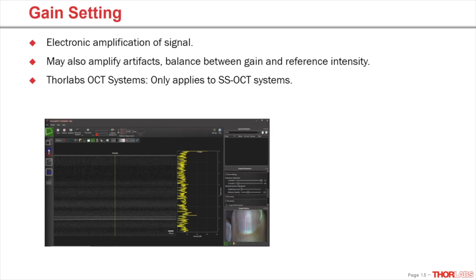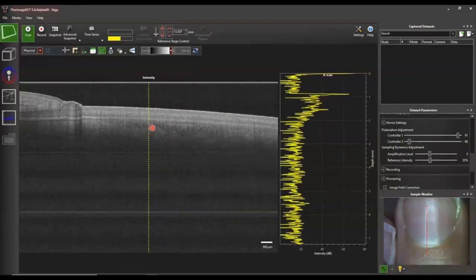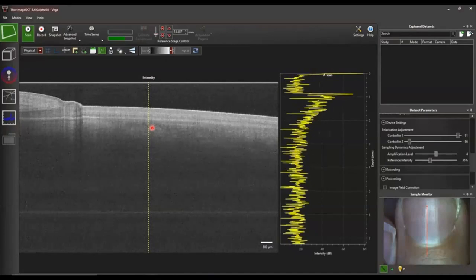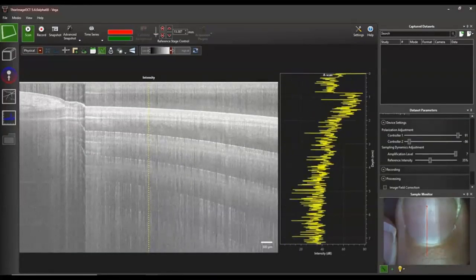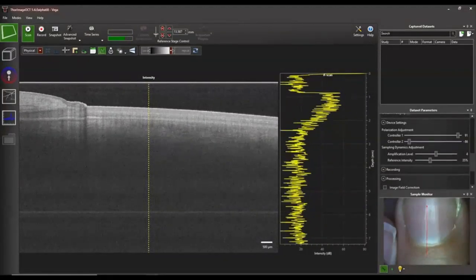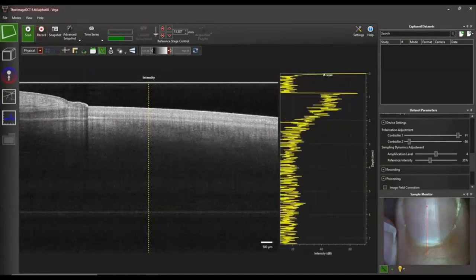Let's talk about gain settings. Gain is an electronic amplification of the signal, but it may also amplify artifacts, so you need to find a balance between gain and reference intensity. For Thorlabs OCT systems, this applies only to swept-source OCT systems — the Vega and HR series. In a video of my fingernail, starting at the lowest gain setting and increasing it, you can image deeper into the sample. However, if the gain is too high you just get artifacts. A good balance in this case is amplification level 4 or 5.